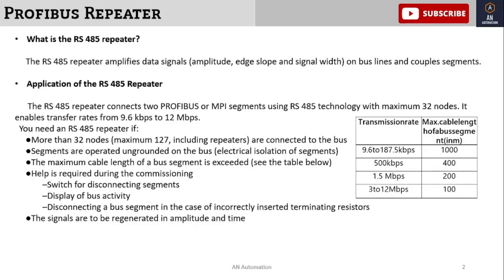The maximum cable length of a bus is extended using the repeater. When the cable length is about to reach 80 to 100 meters, we generally use a repeater — otherwise the signal voltage of the Profibus network will drop and modules beyond 80 to 100 meters will disconnect or not communicate properly with the main system or controller. We use 3 to 12 Mbps for 100 meters, and 1.5 Mbps for 200 meters.